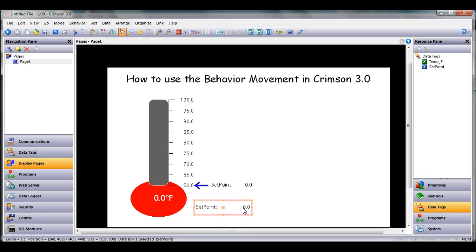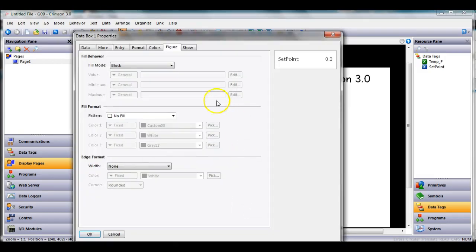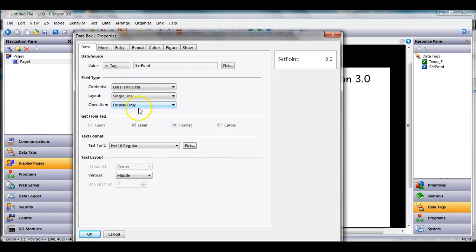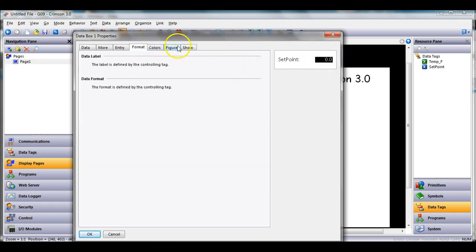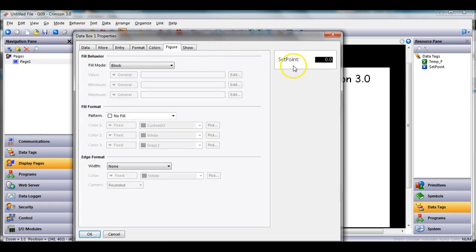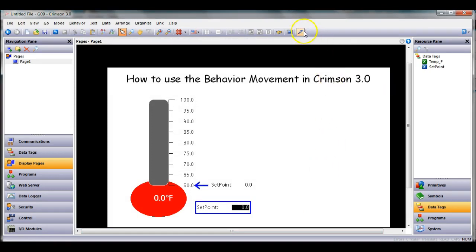I'm going to double click on it, go to the data tab where it says operation, choose data entry. Notice the background color gets inverted. Then I'm going to go to the figure tab, and remember when I teach a class if I have a field that's a data entry, I at least like to give it a border so that the end user knows where to click or tap to get the keyboard to come up. I'm going to give it a blue border three pixels.